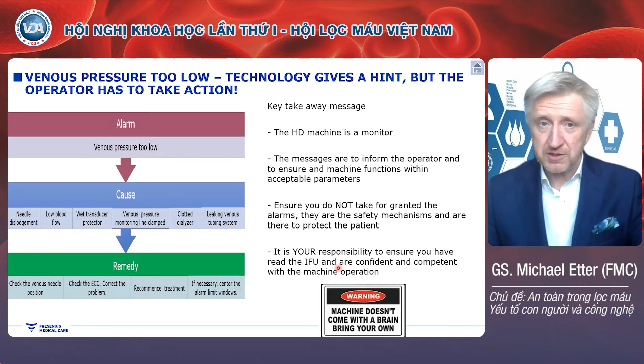It is your responsibility as the operator to make sure that there is a synchronization between the machine advice and your action. I found this funny quote, which I think fits quite nicely. It says, the machine doesn't come with a brain, you still need to use your own. In the future, we may see so-called closed loop systems. They are under development, they're in testing, where basically once a dialysis machine sees an issue, an alarm, it triggers a change in the configuration of the machine to resolve this. But this is something that we will see in the very near future. Today, we have to make sure that if there's an alarm, we deal with the alarm.